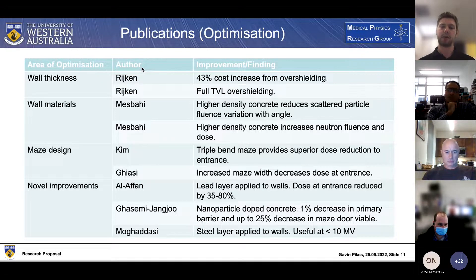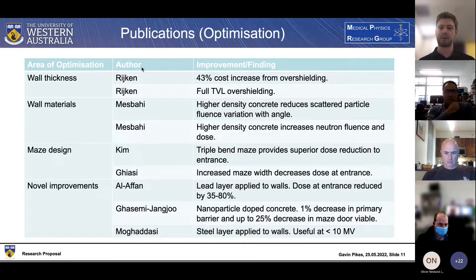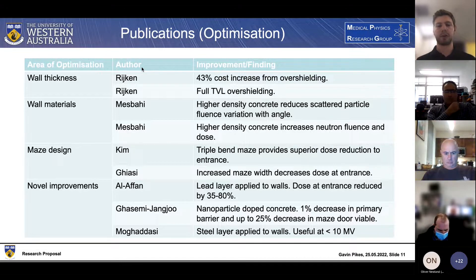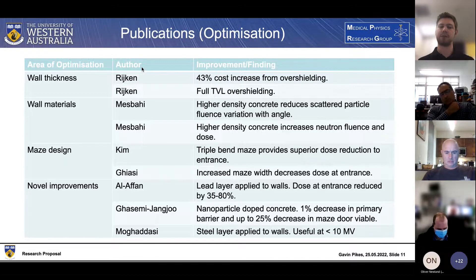The MARY bunker does have a triple bend within its maze, however the first bend isn't a 90-degree angle, so there could be some room for optimization there. Additionally, we can look at the width of the maze corridor - a higher width corridor actually reduces the dose at the entrance as well. In terms of novel improvements, Al-Affan looked at layering the walls of the maze with lead, which resulted in a 35 to 80 percent decrease in dose at the entrance, however again this is with a lower energy beam as above 10 MV we deal with photoneutron problems with high-Z materials.